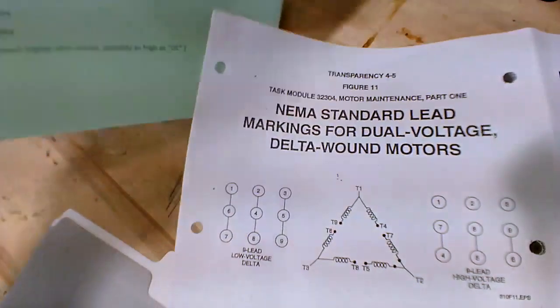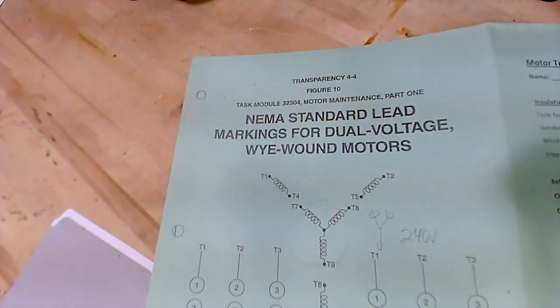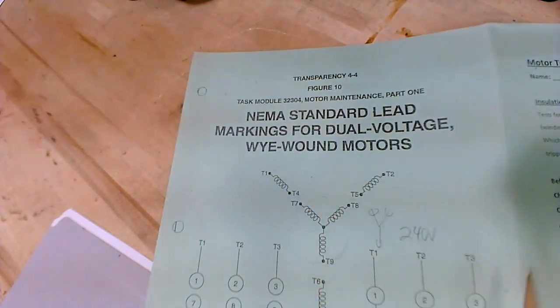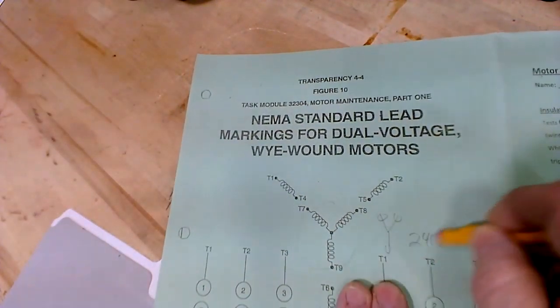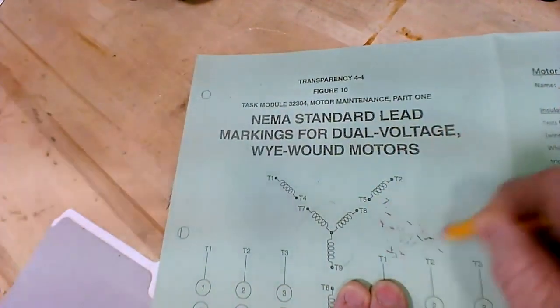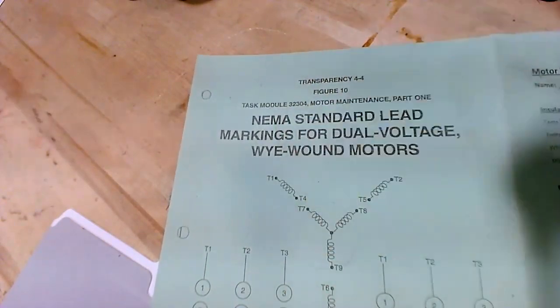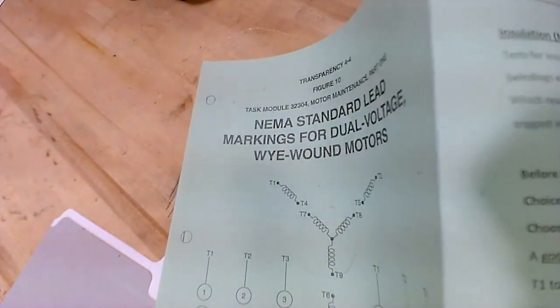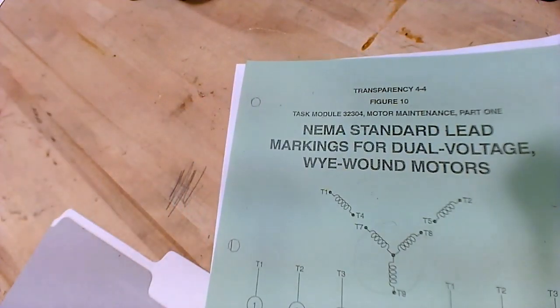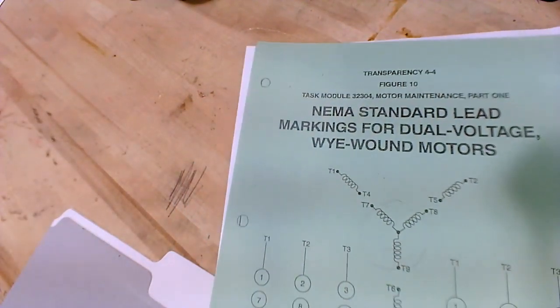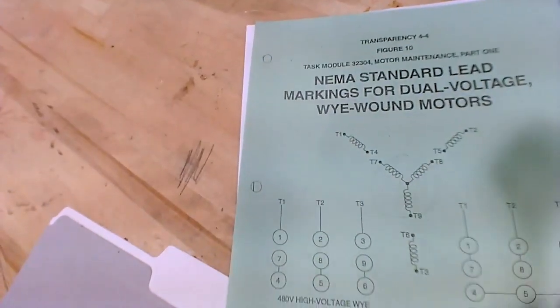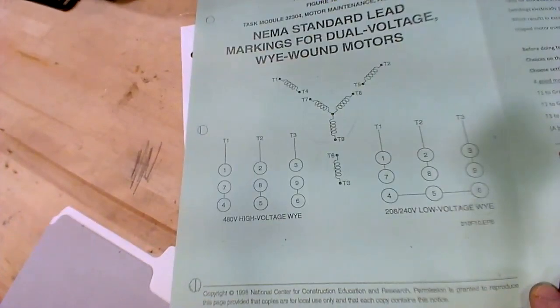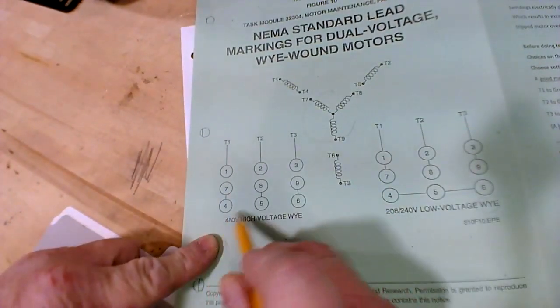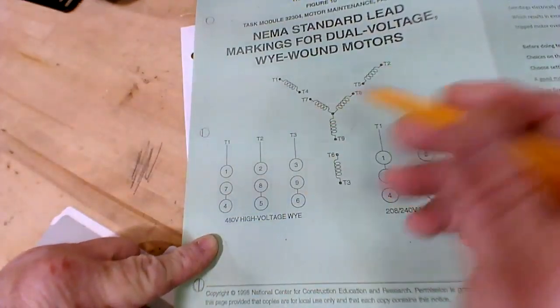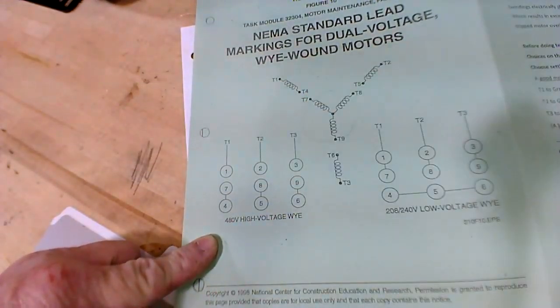And so here, let's back up to the Y configuration. So when we did this, we said we were producing double Y in parallel for 240. So what happens if we hook that motor up to high voltage? The same motor will go high voltage. Let's say we're on 480 volts coming to the machine, and the same motor can run on either one of them. So then you have the incoming power from the starter.